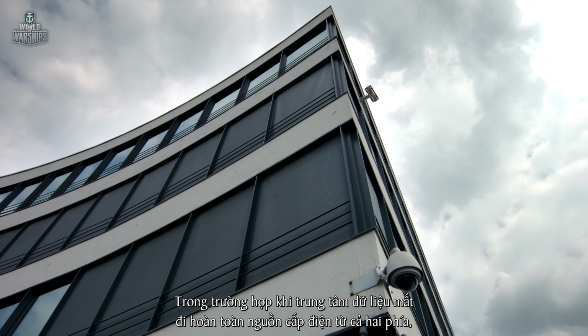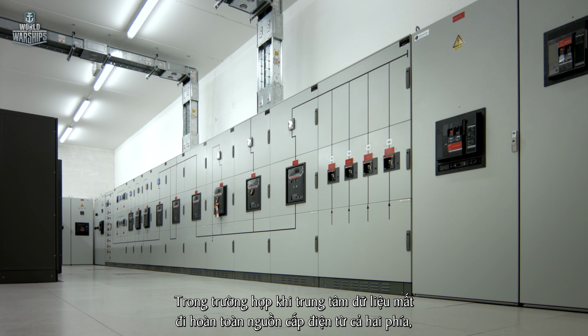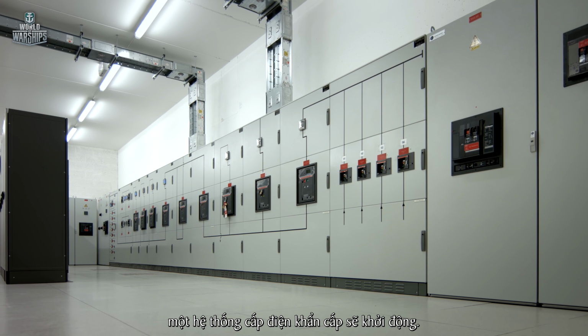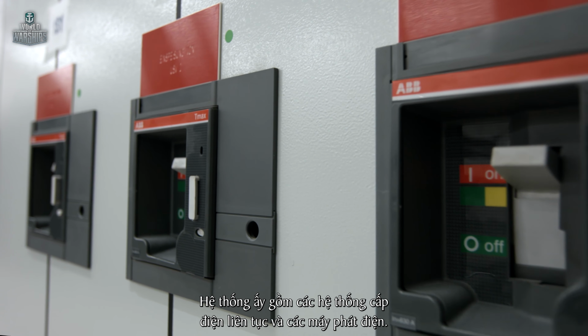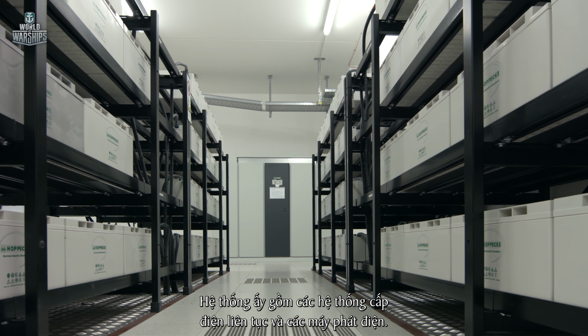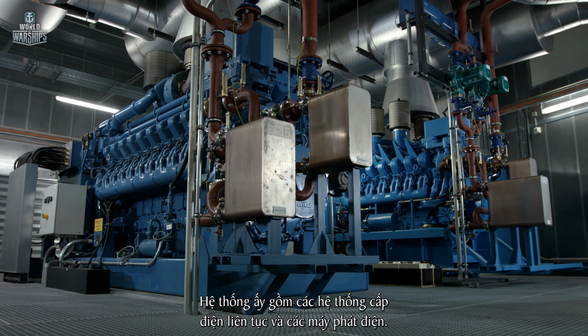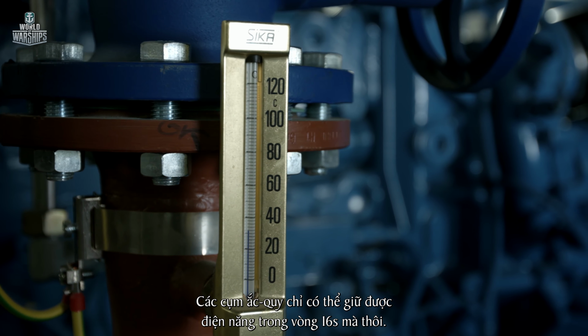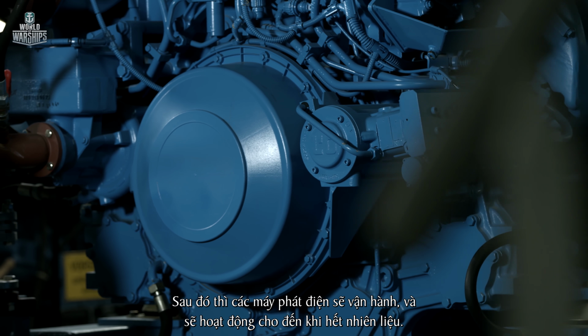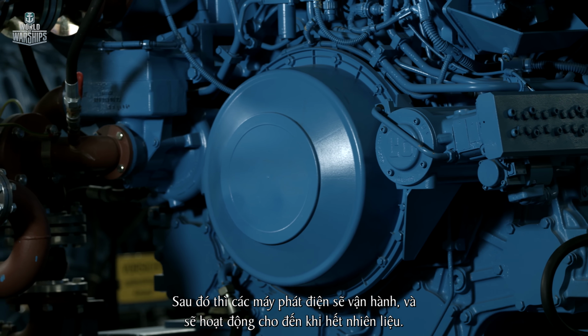In case the data center completely loses the external power supply, the complex has an emergency system. It consists of uninterruptible power supply devices and generators. Batteries only need to keep the data center powered for 16 seconds, until the generators kick in, and they can work as long as there is enough fuel.